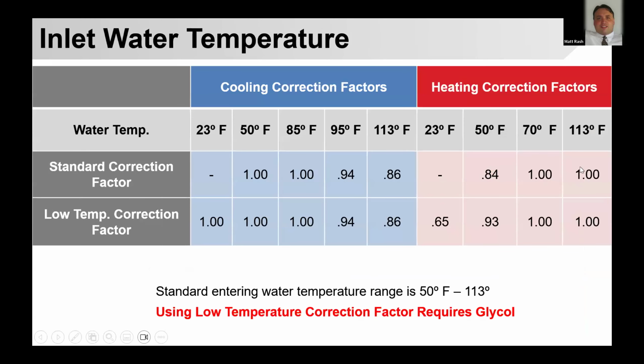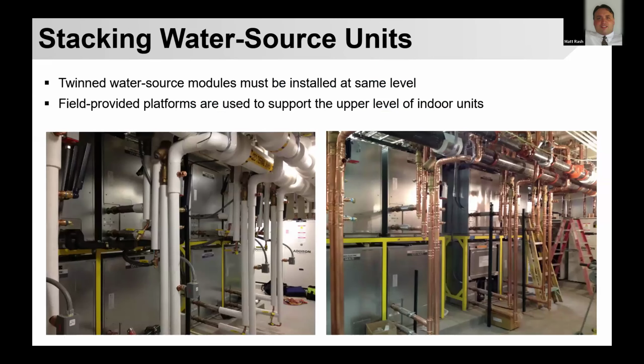You can see typical correction factors that come into play with this gear in rating conditions. So again, this is based on Mitsubishi, but you'll find other manufacturers are similar. We actually have guaranteed capacity data up to 113 degree entering water temperature, and then all the way down to 23 degrees. You can see these capacity corrections in cooling, for instance, only about 86%, so about a 14% loss only at 113 degrees. And then on the heating side, you still have about 65% of your nominal, even at 23 degrees. You do have to consider glycol with these systems. For our equipment, anytime you're going to operate below 50 degrees, we require glycol for freeze protection. So that's obviously important to be mindful of early on in the design.